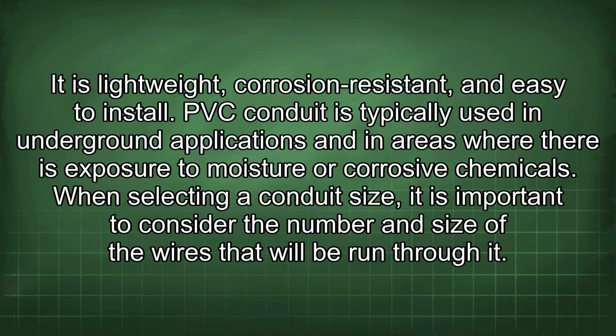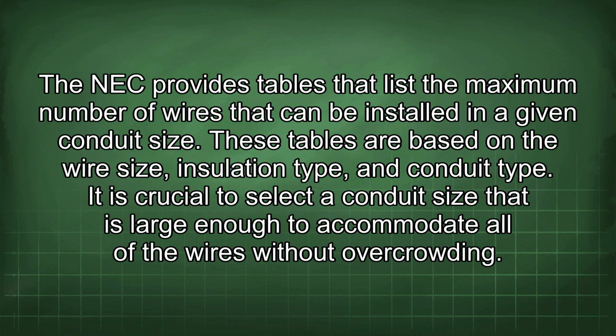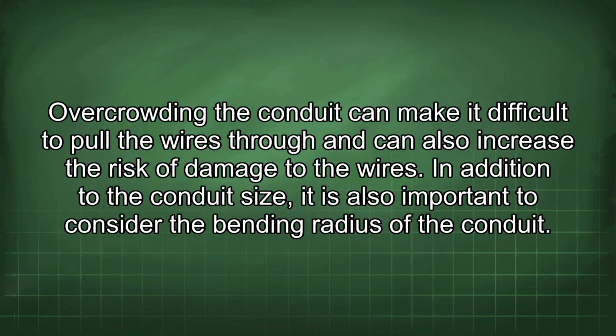When selecting a conduit size, it is important to consider the number and size of the wires that will be run through it. The NEC provides tables that list the maximum number of wires that can be installed in a given conduit size. These tables are based on the wire size, insulation type, and conduit type. It is crucial to select a conduit size that is large enough to accommodate all of the wires without overcrowding. Overcrowding the conduit can make it difficult to pull the wires through and can also increase the risk of damage to the wires.